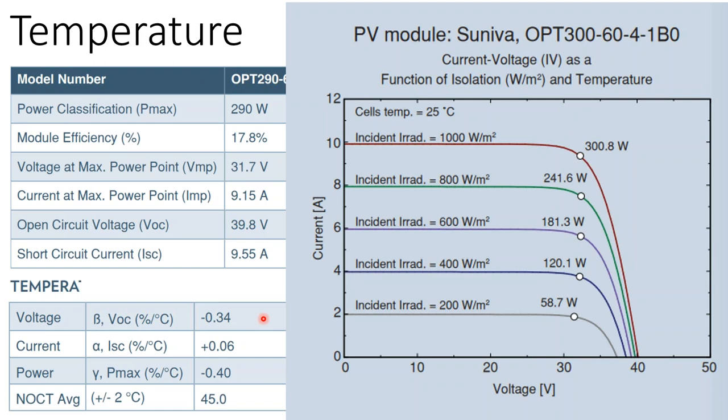And so the design conditions for solar, unless you get an electrical engineering stamp, are the coldest temperature on record. But in the summertime, the hot end of things is less important. The design temperature for the operating temperature is just the average ambient high. It's not the record high. Although if you want to mitigate against rising temperatures, maybe you do pick out a little bit more robust inverter. Not all of these inverters can take being outside in the heat. Even if they're rated for it, it would be better to locate them in a conditioned space if you can.